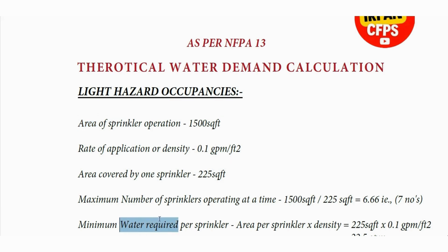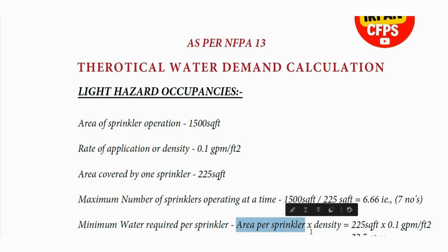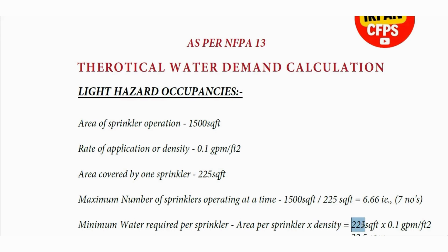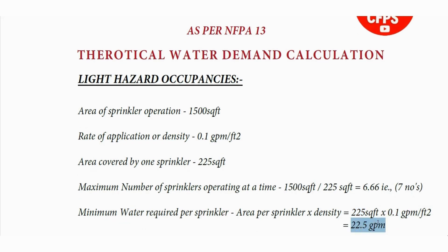Now we are going to calculate the minimum water required from one sprinkler. The formula is: area per sprinkler multiplied by density. Inserting the values — 225 square feet multiplied by 0.1 — we get 22.5 gallons per minute. So 22.5 GPM will be the flow from one sprinkler.